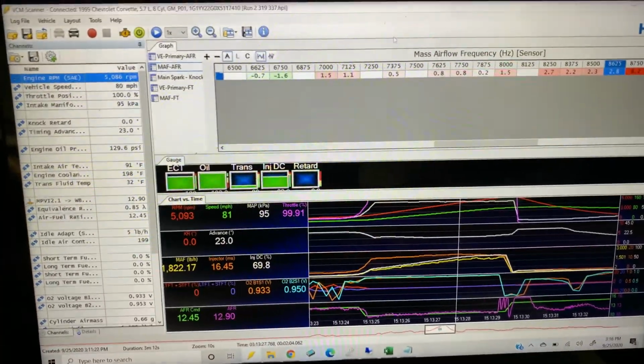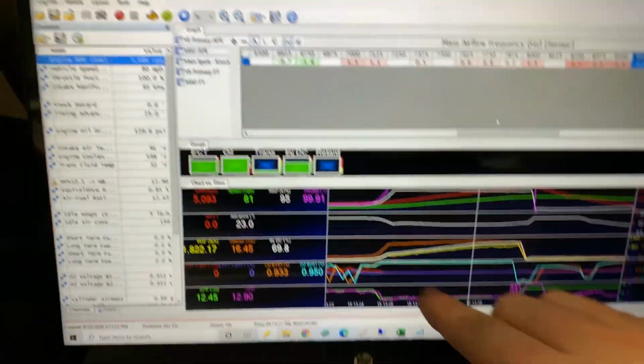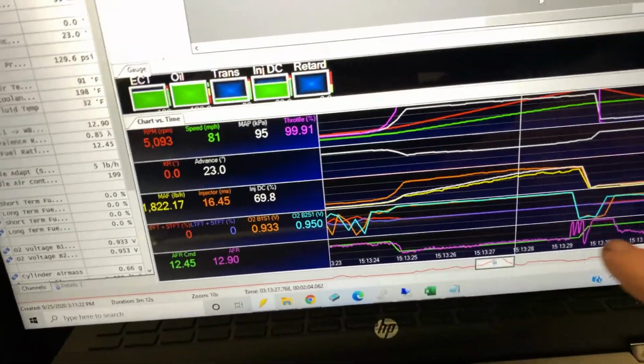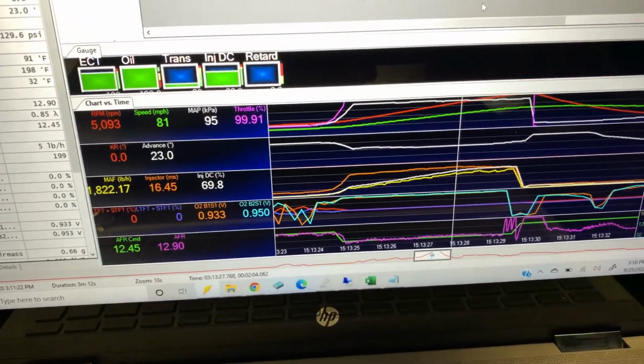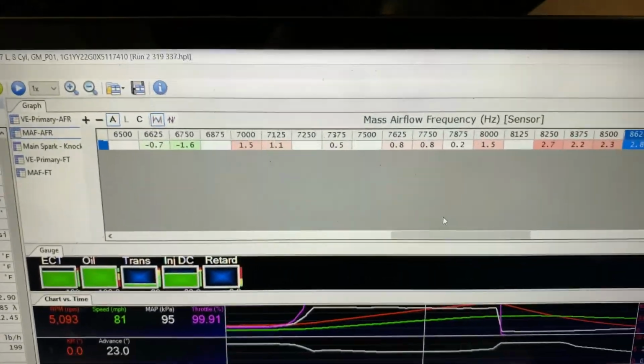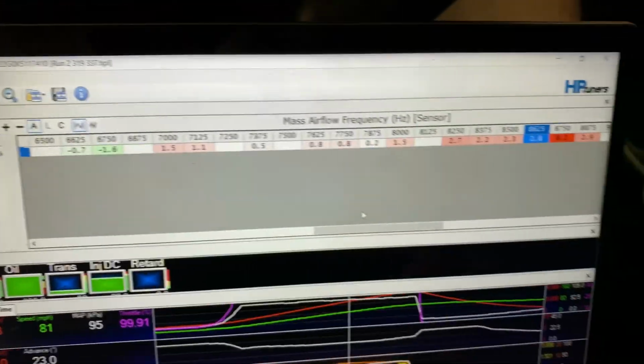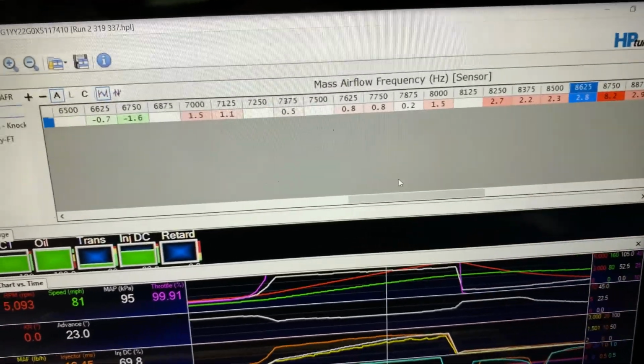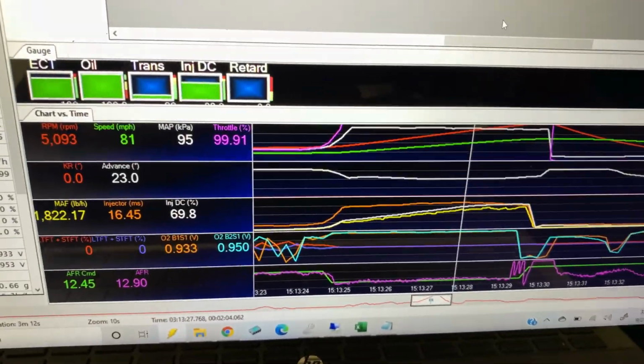I'm going to minimize this and go to the data log view. Fueling is real close. We want to see the purple line lay right on top of the green line. Green line's target, purple is actual. So we've got maybe 2.5% error right now that we need to bake out of that calibration.